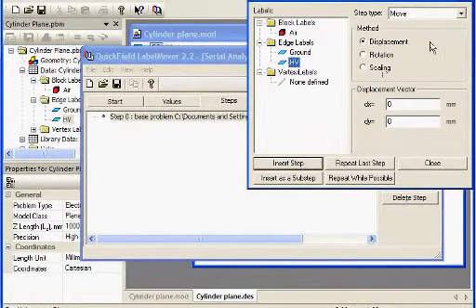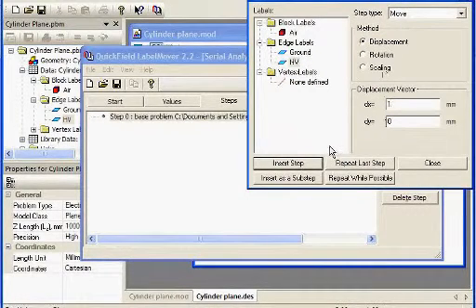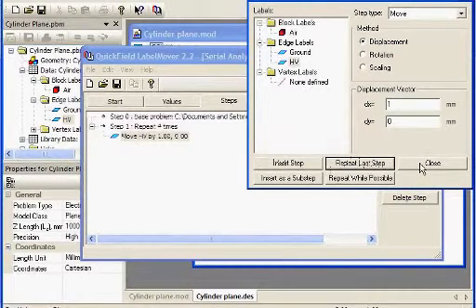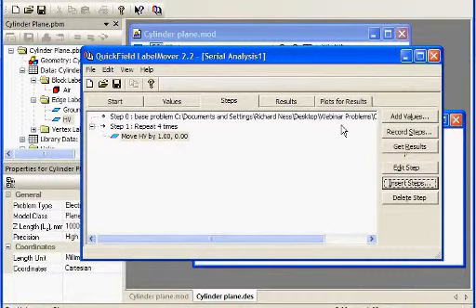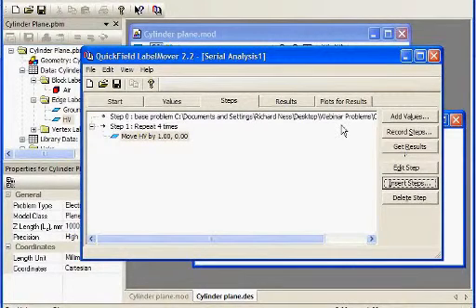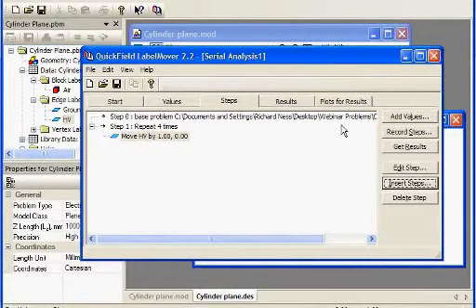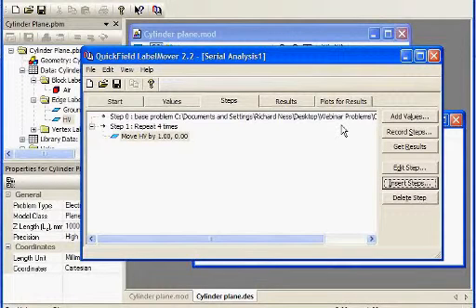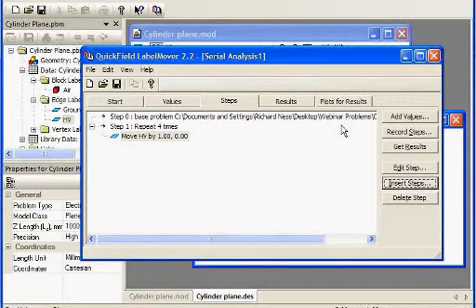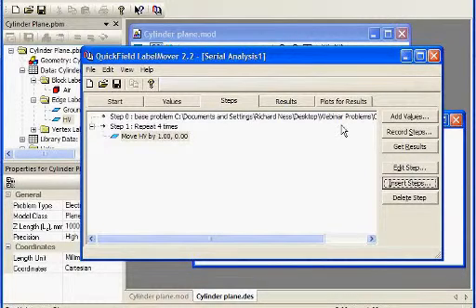Then in terms of the steps, what I'm going to do is basically move that high voltage electrode closer and closer to the ground plane. I can do that for one step. I can repeat that, so I'll go ahead and repeat it four times. But this has application in the real world. Oftentimes in high voltage problems, it's desirable to minimize the stray inductance in the circuit in order to obtain a very fast rise time of the output pulse. On the other hand, in a competing manner, you need to also maintain enough separation between hardware so that you don't have high voltage insulation problems. So it becomes a tradeoff of how small you can make the geometry to keep the inductance down while still keeping it large enough to avoid these insulation problems.